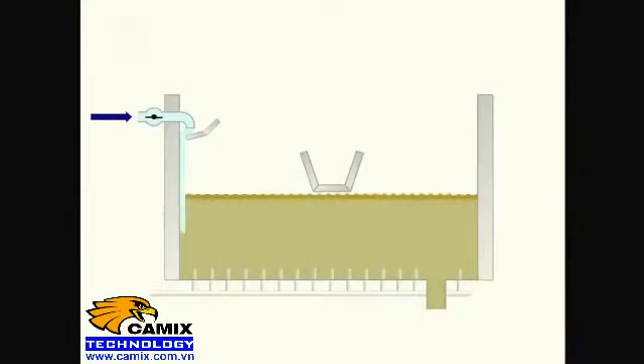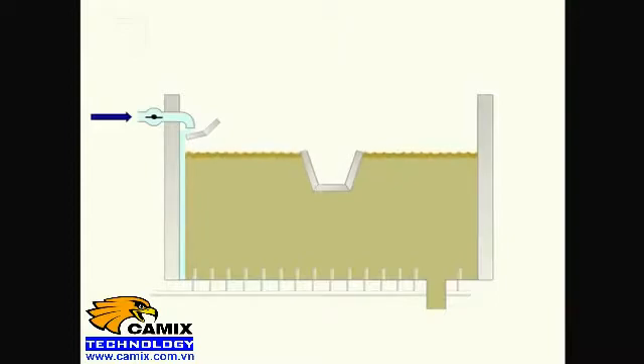Clean water is pumped in, and this fluidises the bed of sand so that the dirt is now in suspension above the sand. The water flow is then increased so that the scum and the dirty water cascade into the outflow trough.